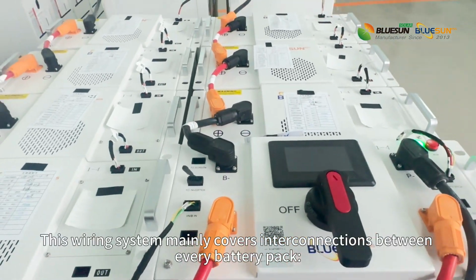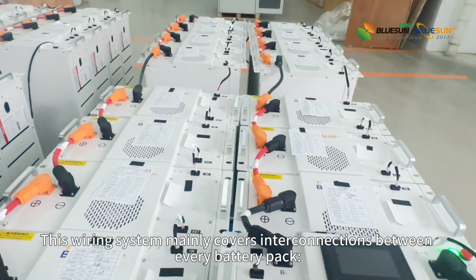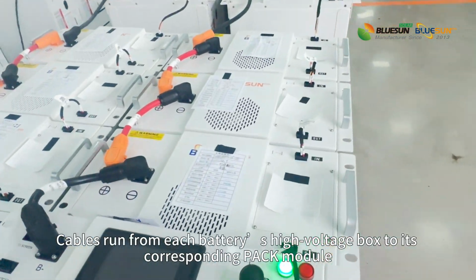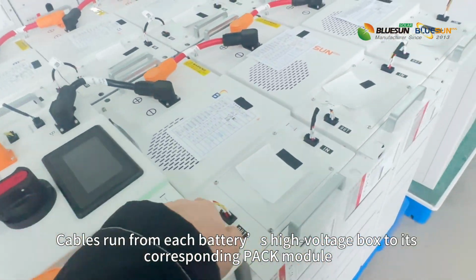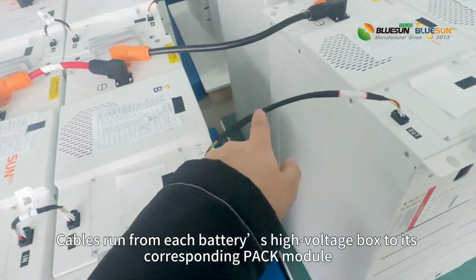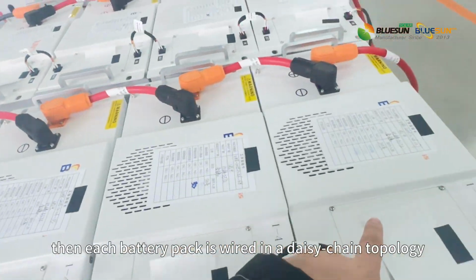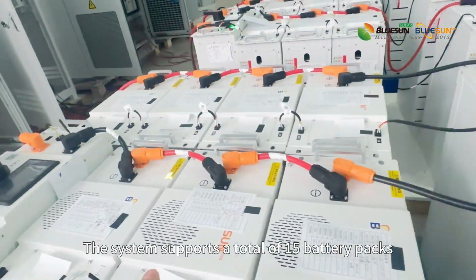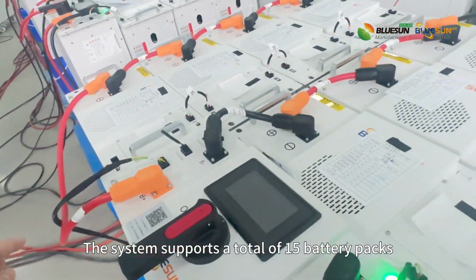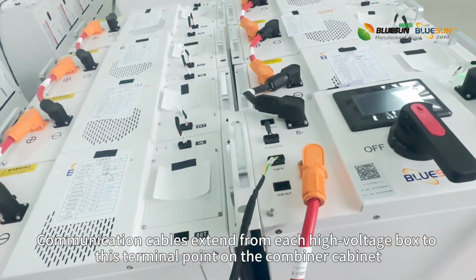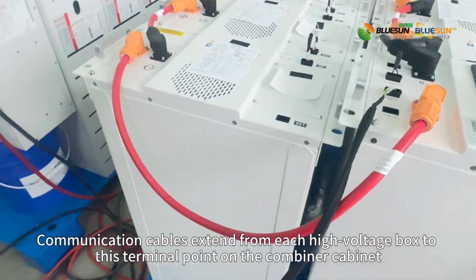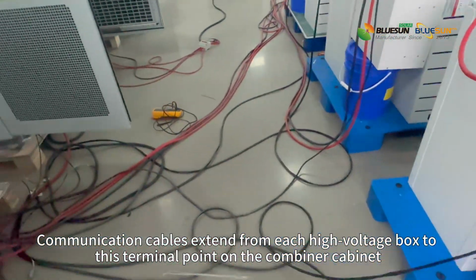This wiring system mainly covers interconnections between every battery pack. Cables run from each battery's high-voltage box to its corresponding pack module. Then each battery pack is wired in a daisy-chain topology. The system supports a total of 15 battery packs. Communication cables extend from each high-voltage box to this terminal point on the combiner cabinet.